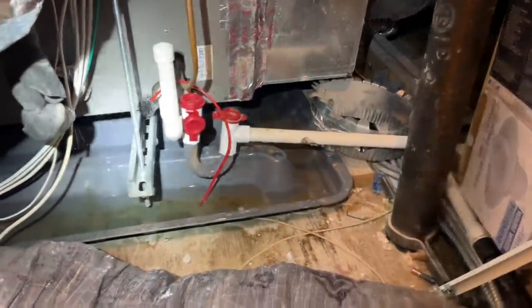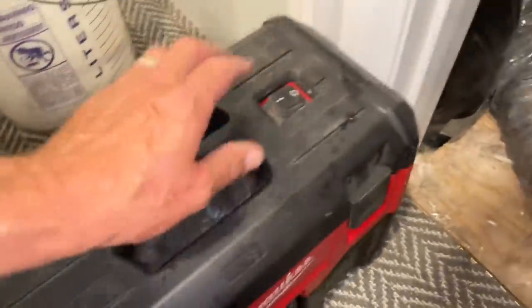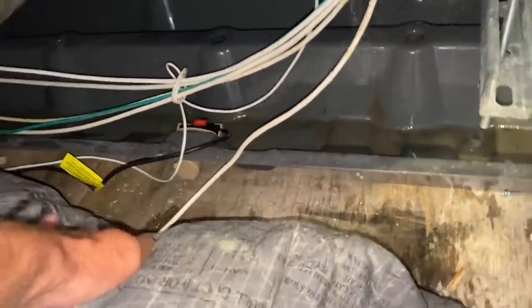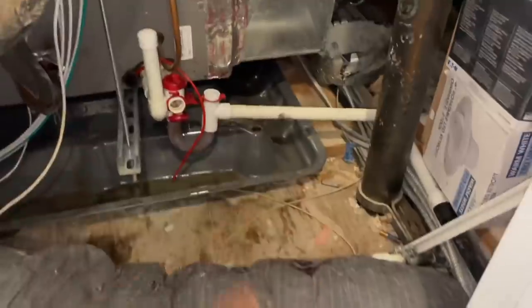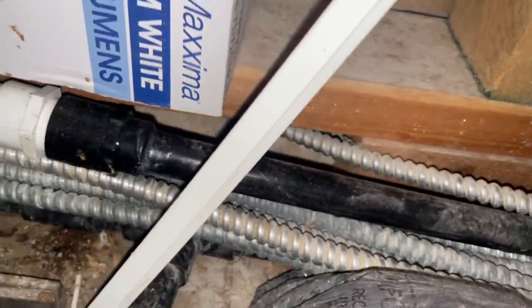I'm going to have to get the shop vac and suck out this water. I'm going to use my Milwaukee. I'll replace that — she didn't cut the cooling circuit off. I sucked out some water, but I'm going to cut a union right there and blow out the drain. They sized down to a half-inch ABS.